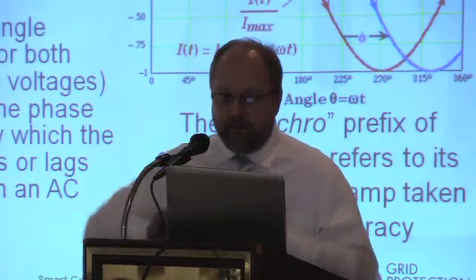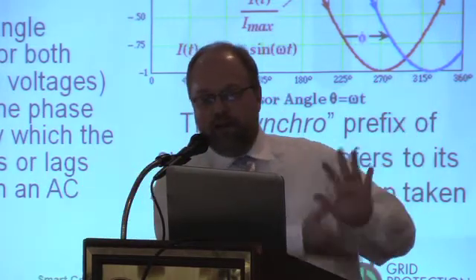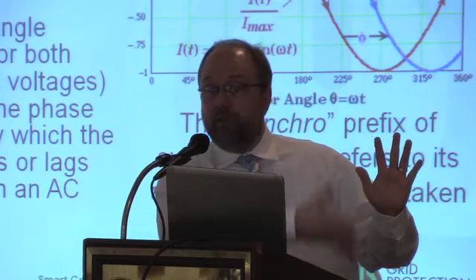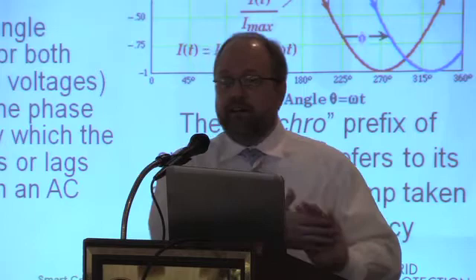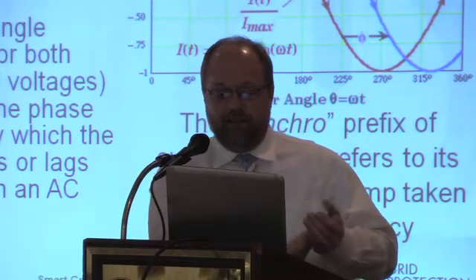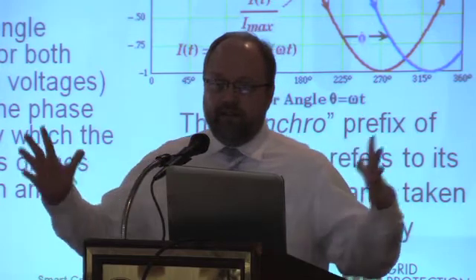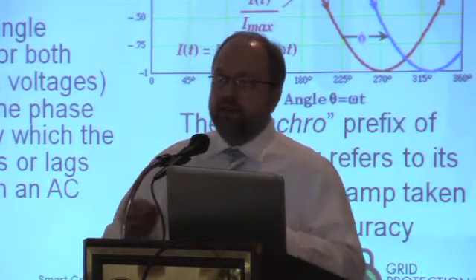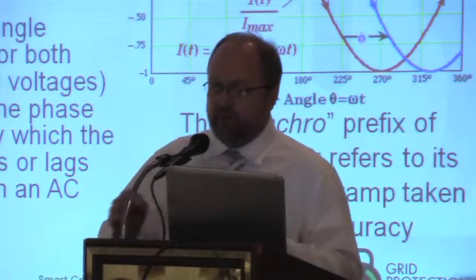Basically, it's a measurement of the electrical system. A phasor is a vector component — two pieces: an angle and a magnitude. The magnitude you're probably familiar with — that's the voltage or the current. The angle is just one more component on this AC system. Measuring the difference between these angles allows you to measure things on the grid that all engineers know about, but we've never had a really good measurement of before.